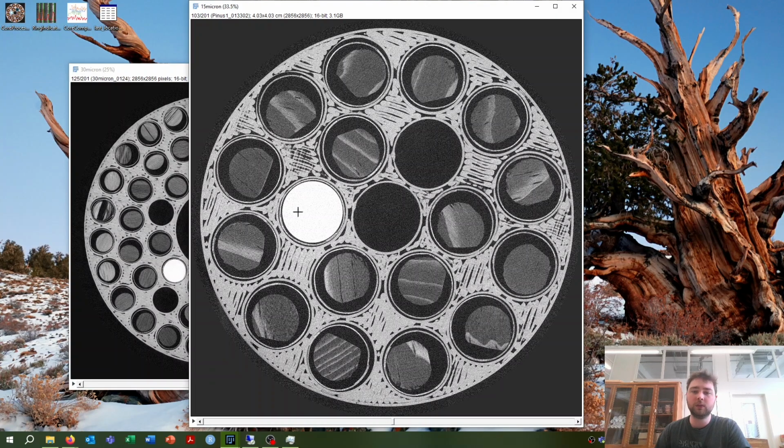And these two are the reference holes. So this is a POM, a type of plastic, which is seen as a pure wood density reference. And here we have air, which is a zero reference. We will use these two references to convert all of these to absolute density values.